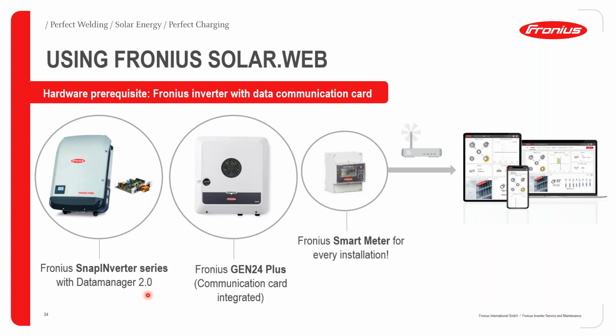For the SNAPINVERTER series, an inverter is able to communicate into SOLAR.WEB provided it has the Data Manager 2.0 integrated, or for the Fronius Gen 24 plus inverters, a communication card now called the pilot. So the Data Manager is for the SNAPINVERTER series, and the pilot is for the Gen 24 plus inverters, coming integrated or embedded as a standard.